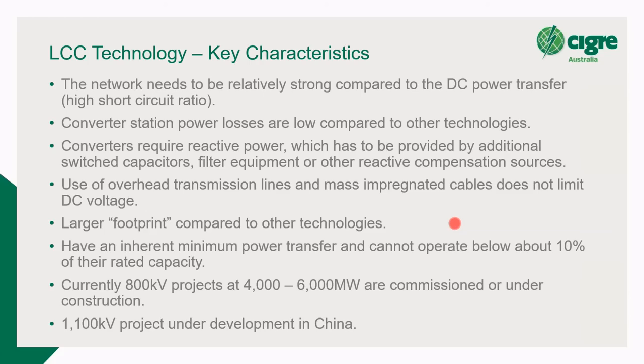Overhead lines, the LCC process does allow the control of the DC current to close to zero, so you can block the converters and potentially restart. So that's why they're very commonly used for overhead line, but they do have a large footprint. The converters can require a fair amount of land.